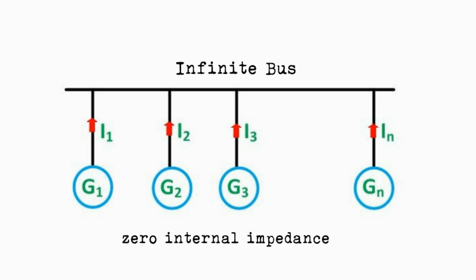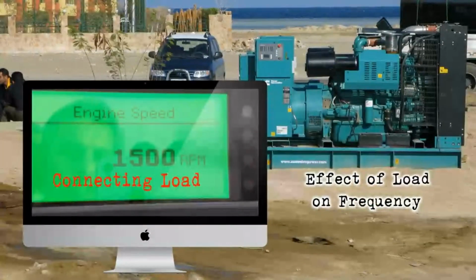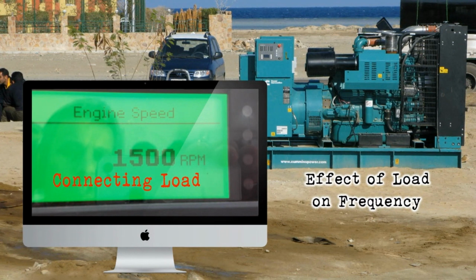Here I made a little video for you. This is a diesel generator I tested. I'll make the video slow motion so that you will notice that when you connect the load, the speed, which is supposed to be 1500 RPM, revolutions per minute. This diesel generator's alternator has 4 poles, so the number of pole pairs is 2, which will lead to 1500 revolutions per minute. Now we'll see when we connect the load how the speed will drop.